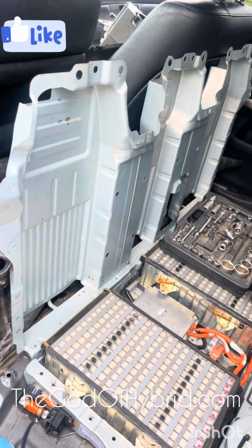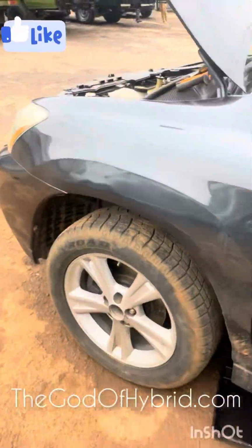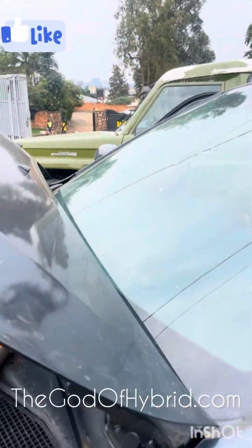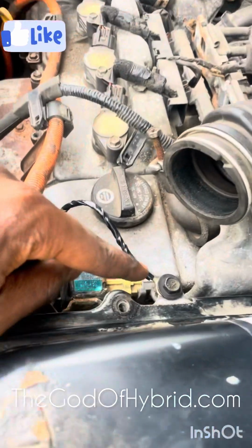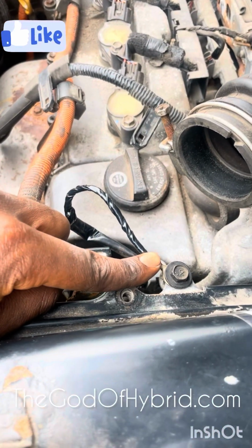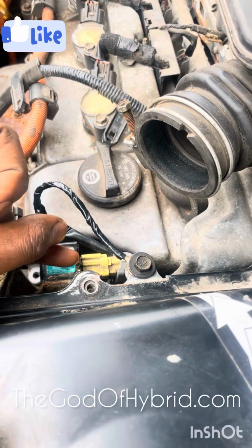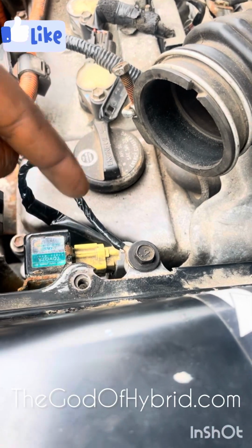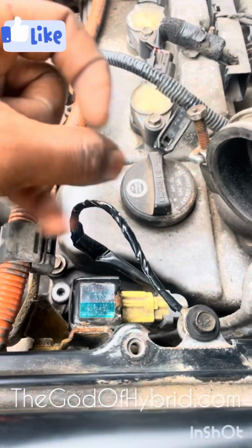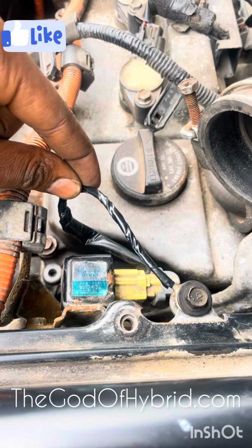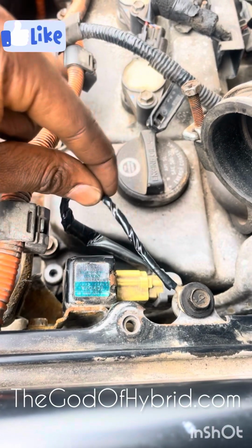Everything seemed fine until I went here. I read the continuity from the service plug grip to the ground cable placed on the inverter. When I read the continuity, I found the wire had corroded inside - there was internal damage in the insulating link itself, the wire.